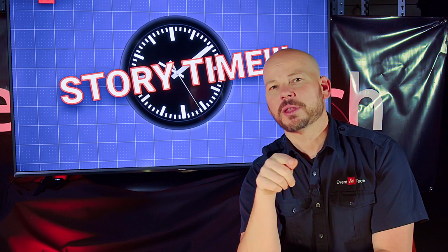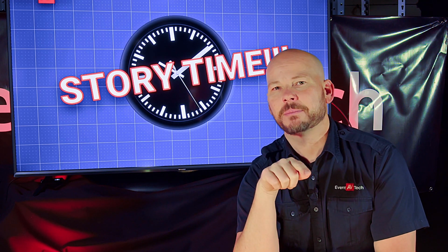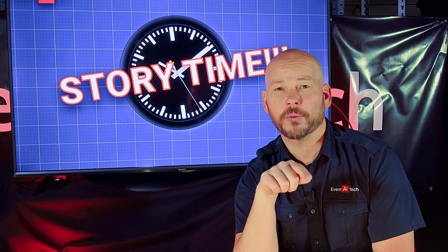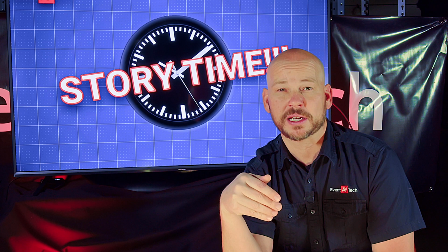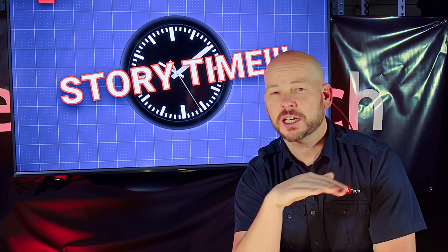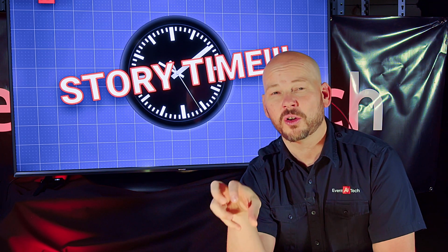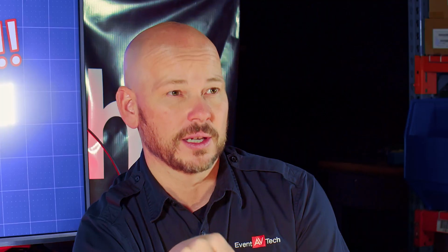But they put the motor shades inside the panel with the power for the PA, so for the actual speakers themselves. And it didn't get caught by anybody until the grand opening event. They had all the shades closed because they wanted this big reveal of downtown.